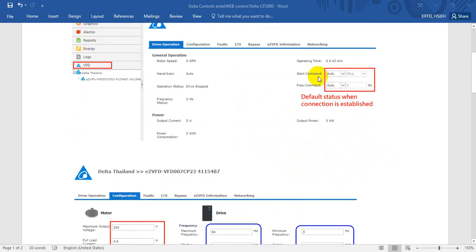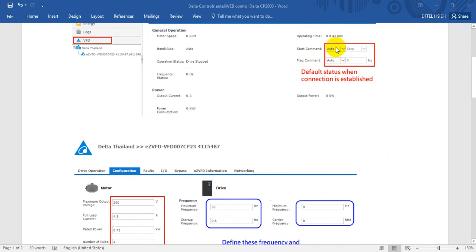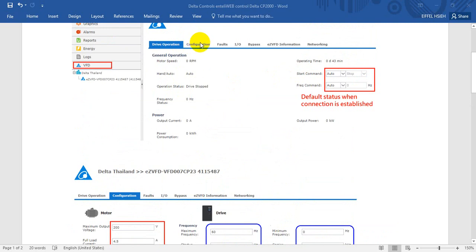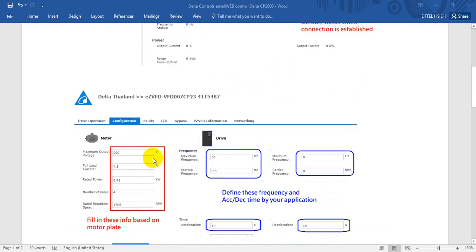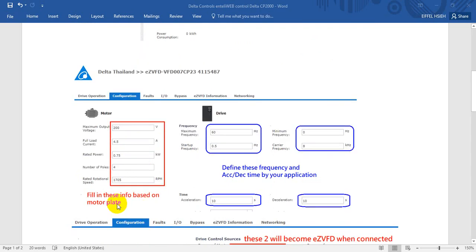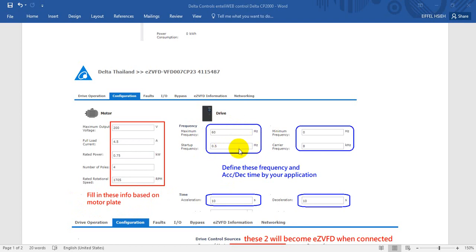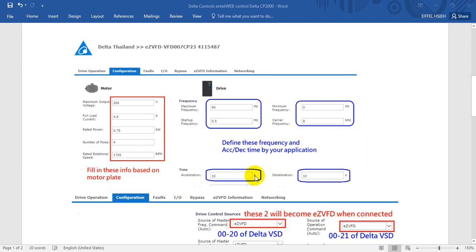Later you will find this one is the same as Delta VSD parameter setting. Then we go to the second page of configuration, so you can fill in some basic motor parameters like the voltage, current, and how many poles and speed of this induction motor. Basically you just fill in this information following the motor nameplate. You can define the maximum frequency and the startup frequency, and also the minimum and carrier frequency. Here is the acceleration and deceleration time, so the unit is based on seconds.